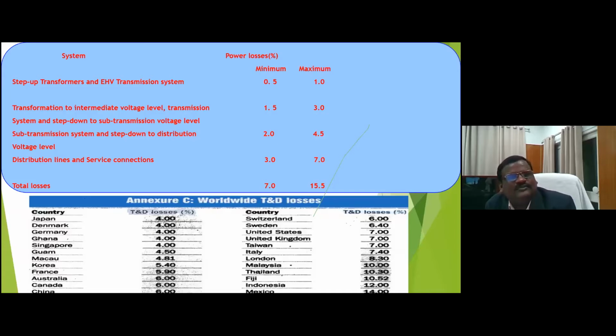The government has taken action for energy to all, using step up transformers for EHV transmission system. Especially on the generation side, minimum losses to maintain are 0.5 to 1%. Transformation to intermediate voltage level, stepping down to sub-transmission voltage level such as 400 kV or 220 kV, should be 1.5 to 3%. The sub-transmission system stepping down to distribution voltage level, 220 kV to 110 kV, 110 kV to 11 kV, should be 2% and 4.5%. The distribution line and service connection, especially 11 kV to 0.4 kV, is 3 to 7% maximum. The government has given direction to minimize losses, with the US benchmark of 7% and a maximum level of 15.5%, specifying how much loss to maintain at every stage.